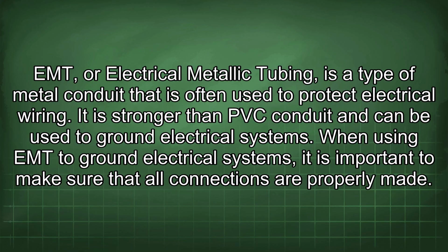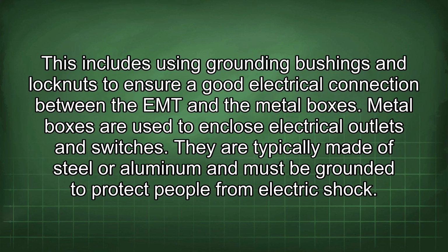When using EMT to ground electrical systems, it is important to make sure that all connections are properly made. This includes using grounding bushings and lock nuts to ensure a good electrical connection between the EMT and the metal boxes. Metal boxes are used to enclose electrical outlets and switches. They are typically made of steel or aluminum and must be grounded to protect people from electric shock.